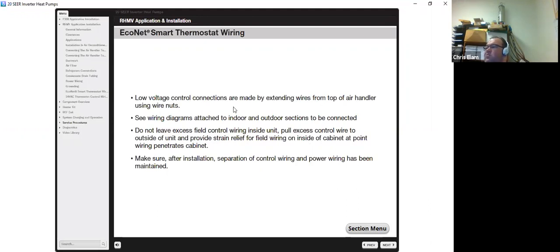See wiring diagrams attached to the indoor and outdoor sections to be connected. On the air handlers, you will have a multitude of wires, so make sure that you verify which wire goes to which terminal. Do not leave excess field control wiring inside the unit. I've seen guys pull it through and they'll have an extra 2 or 3 feet wrapped around inside the unit. Once you pull it through, pull it tight, make your connections. Make sure after installation, separation of the control wiring and power wiring has been maintained. If you get them too close, you can and probably will end up with communication errors.